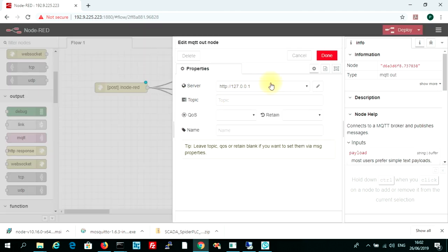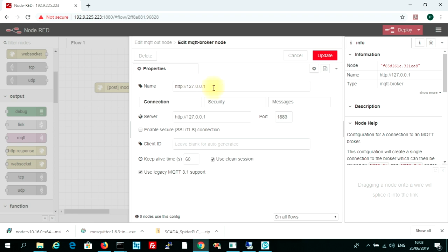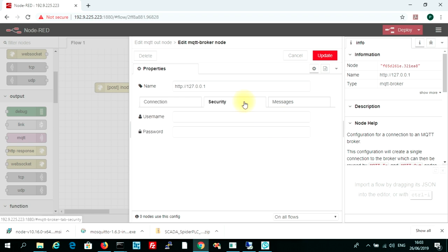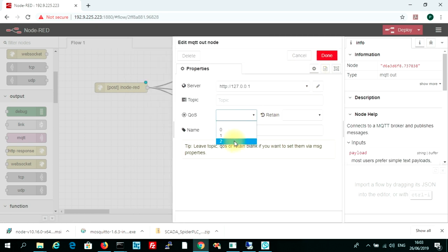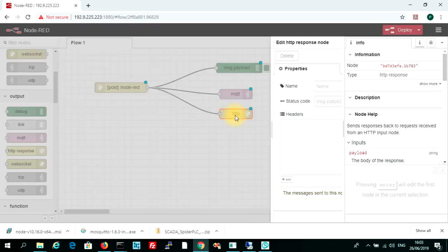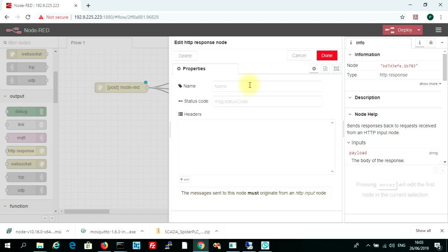The Mqtt is an important thing, so we will first enter the correct URL. So localhost is correct in this case because we have everything located on the Beckhoff PLC. The port is okay. Security username password we will not use for this demo. We make update, we choose quality of service 2, retain don't need, so that will be just fine. And for the HTTP, this will just return the status message.